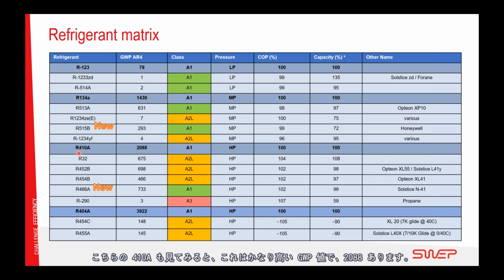We can also look into R410A here. It has a quite high GWP of 2088. It has the advantage of being A1, non-flammable. Candidates here is R32, quite low GWP of 675. However, it is mildly flammable. It has good properties with regards to COP and capacity. So you can see a slightly higher COP and capacity, of course, depending on the operating conditions. R454B is quite interesting, 466 as GWP, also A2L, very similar to R410A in capacity and efficiency.